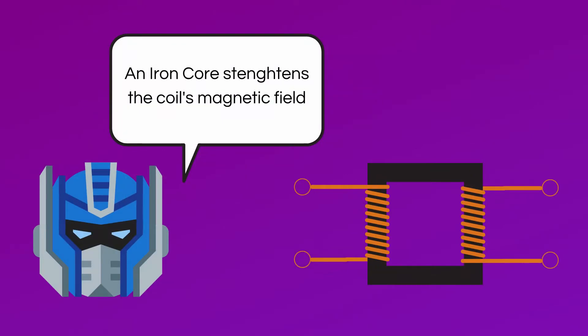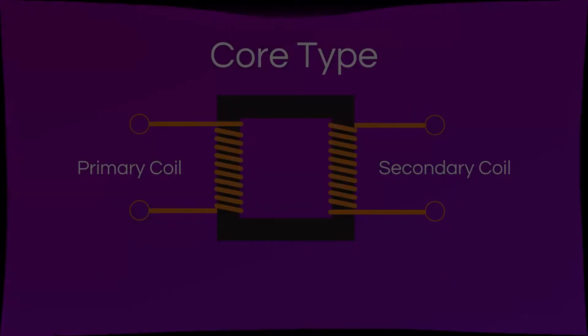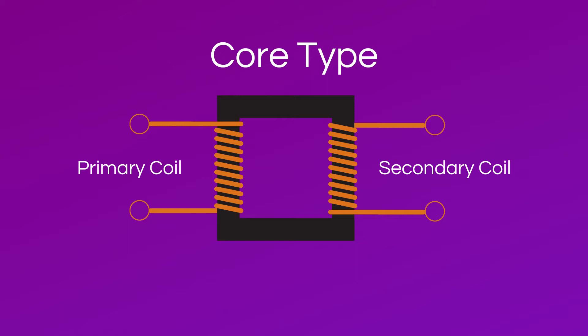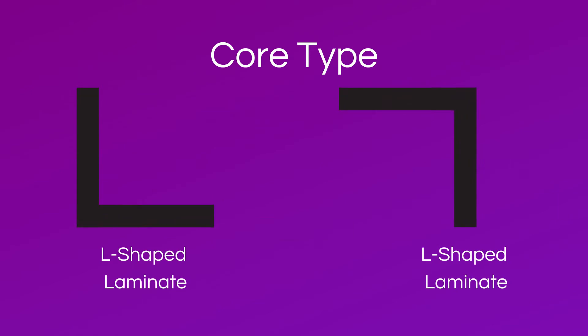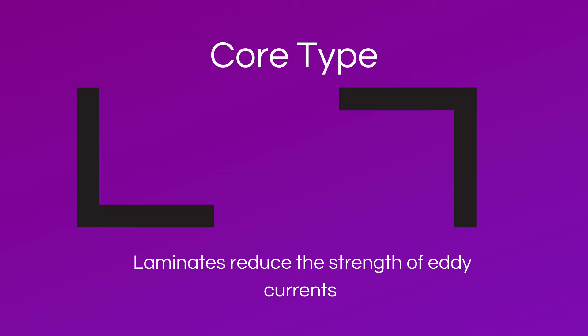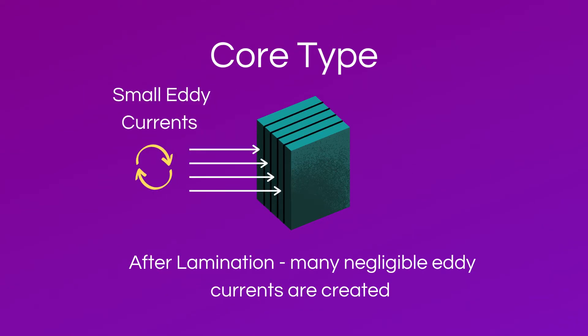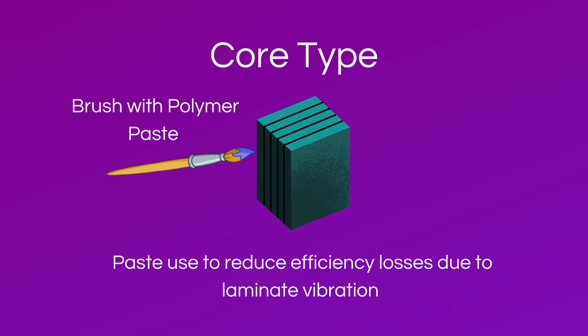The primary and secondary coils are wound around an iron core to strengthen the coil's magnetic field. The three main core structures are core type, shell type, and toroid type. The core type single phase transformer looks like a square with the primary coil on one side and the secondary coil on the other. It is actually made up of very thin L-shaped iron laminates that form a square when combined, along with a bobbin. Laminates are used to reduce the strength of eddy currents — an eddy current is created in a conductor by a varying magnetic field. By splitting the overall surface area into laminates, many weak eddy currents are created instead of one strong eddy current powerful enough to reduce the overall efficiency of the transformer. A polymer paste is brushed around the laminates to secure them so that there will be minimal efficiency losses due to vibrations.